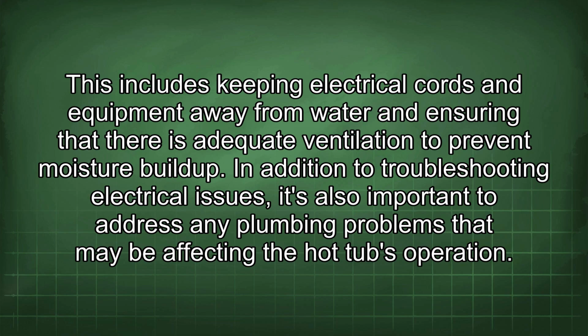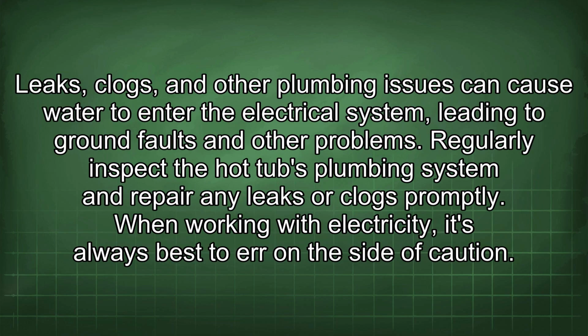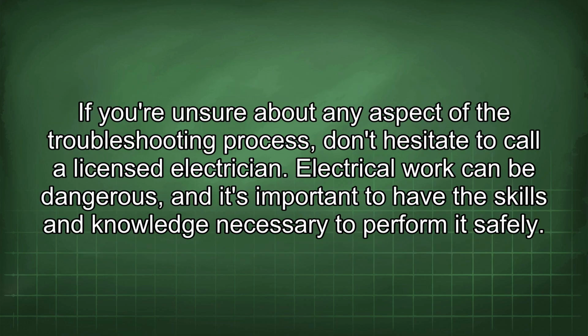In addition to troubleshooting electrical issues, it's also important to address any plumbing problems that may be affecting the hot tub's operation. Leaks, clogs, and other plumbing issues can cause water to enter the electrical system, leading to ground faults and other problems. Regularly inspect the hot tub's plumbing system and repair any leaks or clogs promptly. When working with electricity, it's always best to err on the side of caution. If you're unsure about any aspect of the troubleshooting process, don't hesitate to call a licensed electrician. Electrical work can be dangerous, and it's important to have the skills and knowledge necessary to perform it safely.